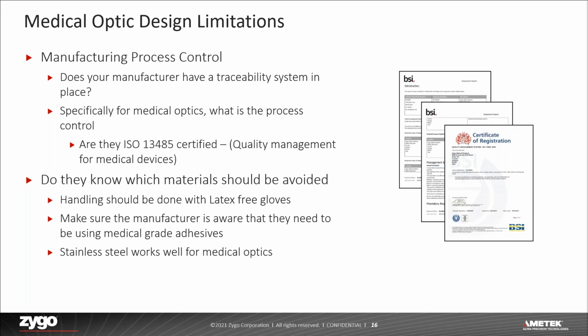Additionally, your supplier should be aware of what manufacturing needs are acceptable for medical applications. This may be as simple as using latex-free gloves in fabrication and assembly. You also want to make sure your supplier considers the acceptable materials that are used in your medical device. As adhesives are frequently used in optical systems, understanding which adhesives are medical grade is critical. If process flow or material considerations are not followed, the results may be catastrophic.